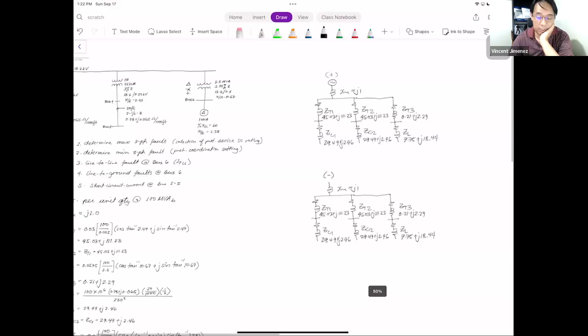Then, to establish the zero sequence at bus 6, how do we do that? Start from the utility. The utility is always given as Y, solidly grounded. Rarely is it given as delta. So we start at the utility.